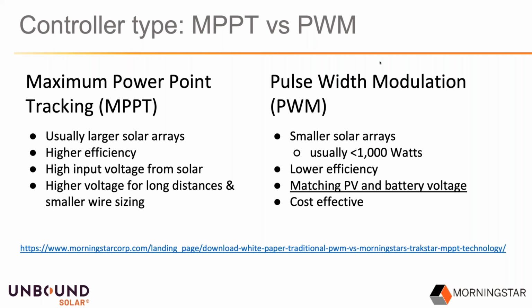If you're going certainly anything over 50 feet from the PV array to the batteries, you'd probably be looking at an MPPT. And when you get up to several hundred feet, let's say more than about 200 feet, or about 60 meters, that's when you'd start looking at a high voltage MPPT, such as a 600 volt controller that's really going to optimize that power transmission for longer distances.